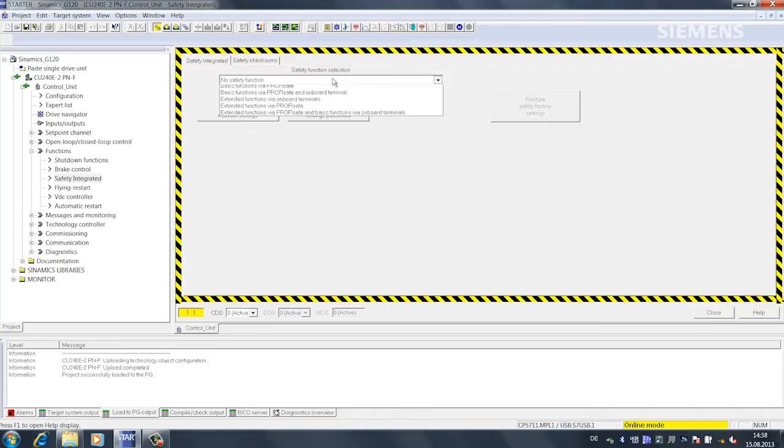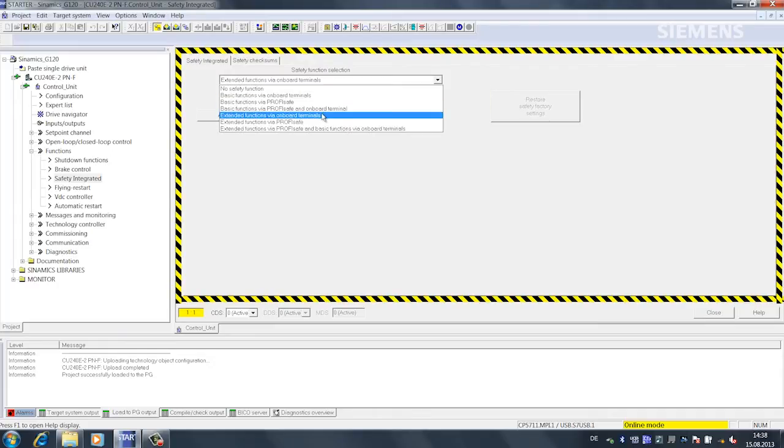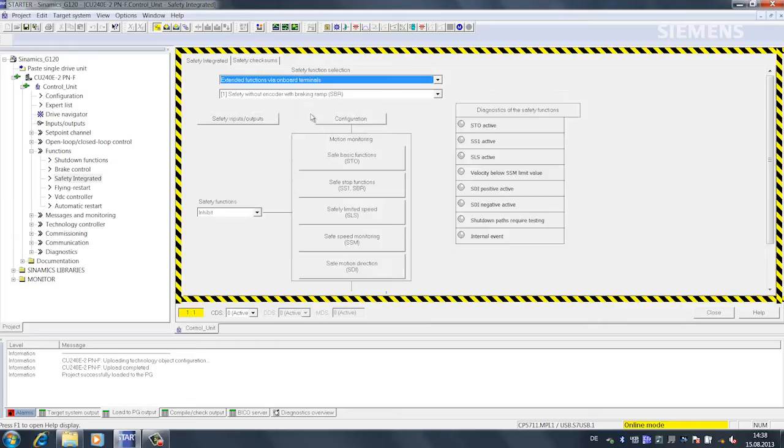I select the extended function via onboard terminals. SS1 is an extended integrated safety function. In a SINAMICS G120 CU240 E failsafe, only Safe Torque Off is a basic function.